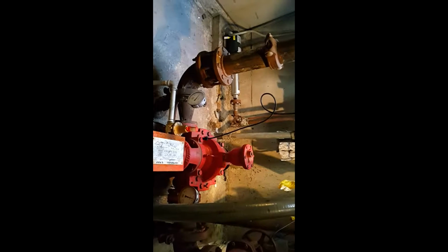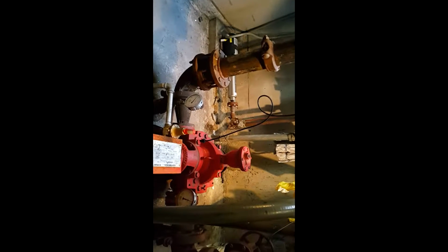And if it starts spitting up air or water, that means this valve right here is closed because it's sucking air. You sucked it dry, and there's a chance that you might spin it out of control. Just like a straw, when you suck, the first part is nothing but air, and then you get fluid moving. So that's what that's for.